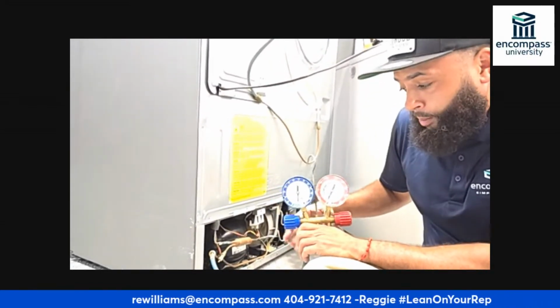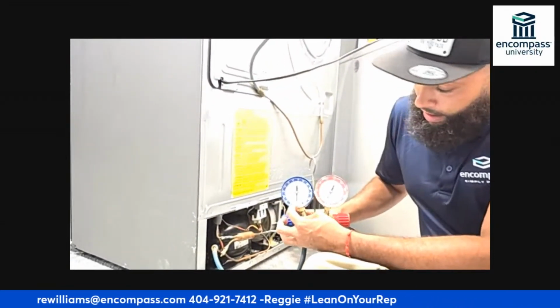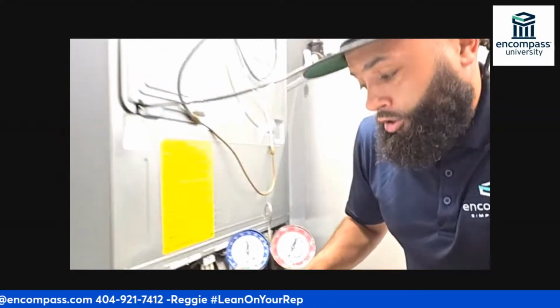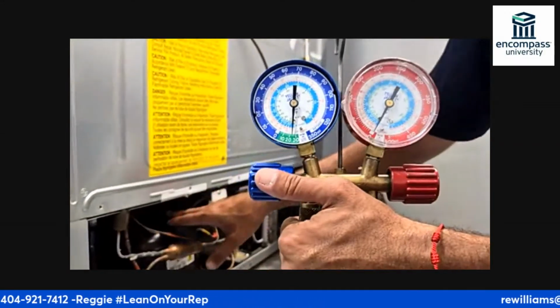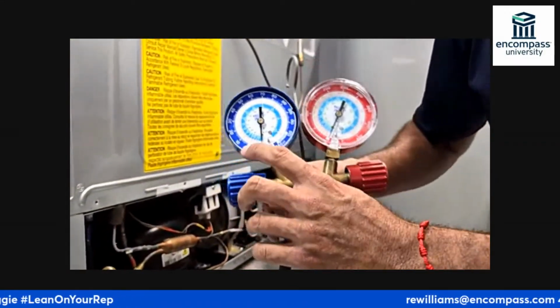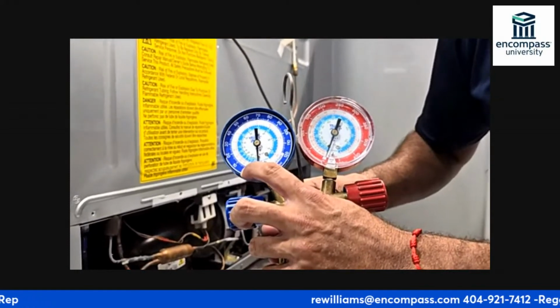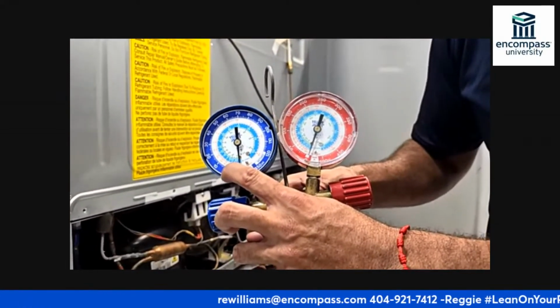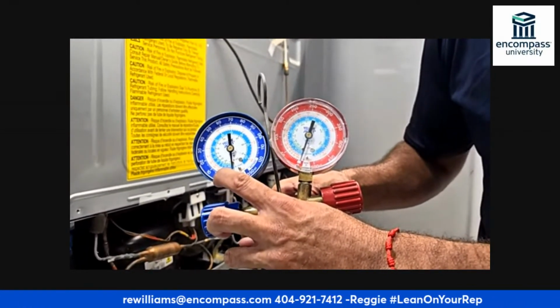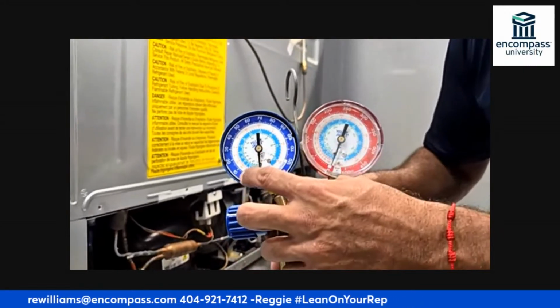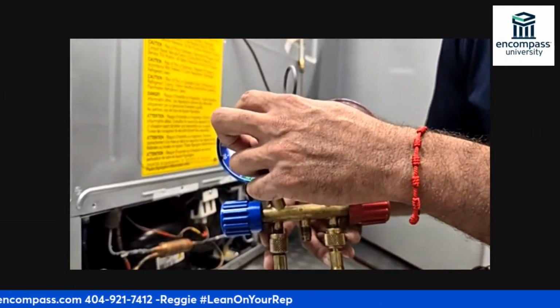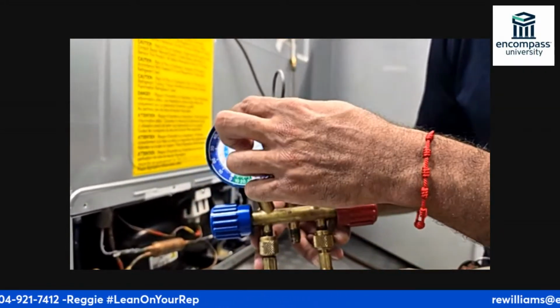For future purposes, if you tap into a fridge while the compressor is running, the gauge should be at 0. When you unplug it and the unit's still connected, you'll see the gauge rise. It'll take a few minutes, but it'll rise and settle somewhere up in here.